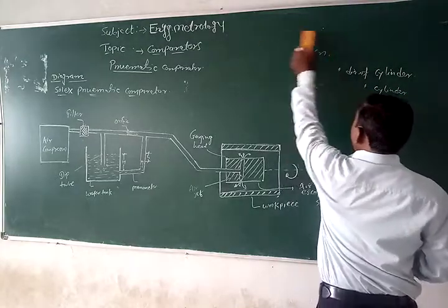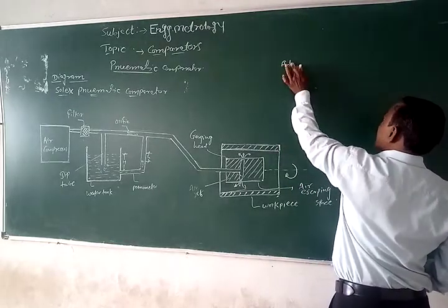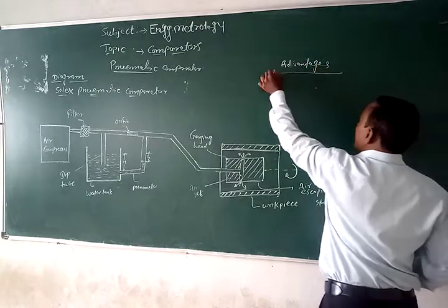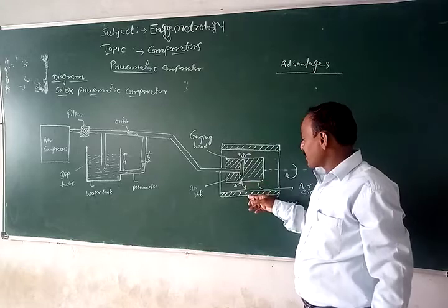How is it advantageous? The advantage is that there is no contact surface with the workpiece. The air jet, the gauging head, has no contact with this workpiece.